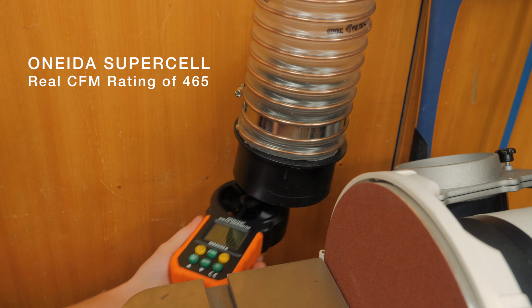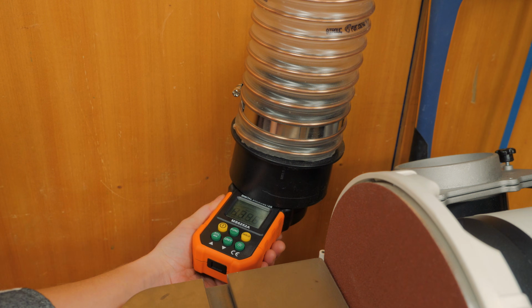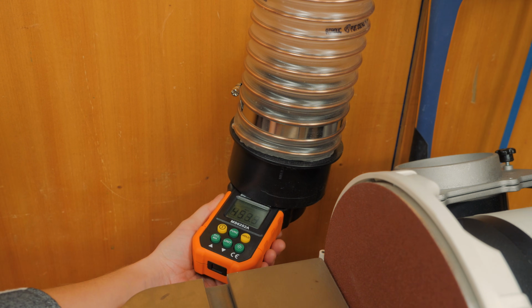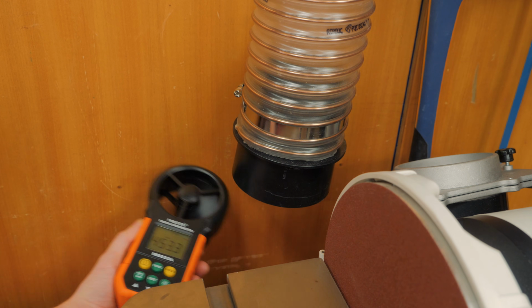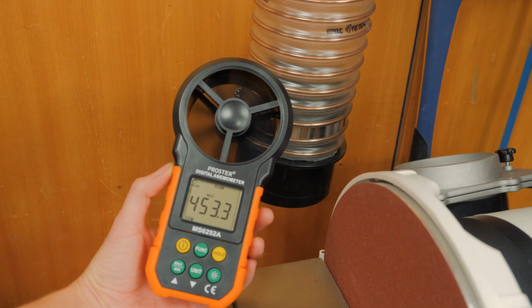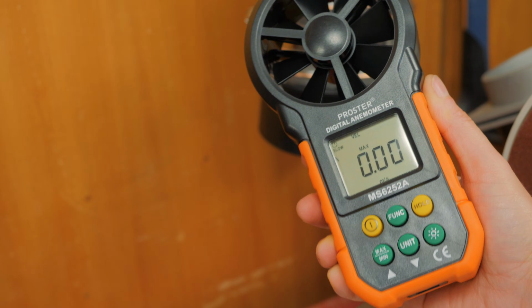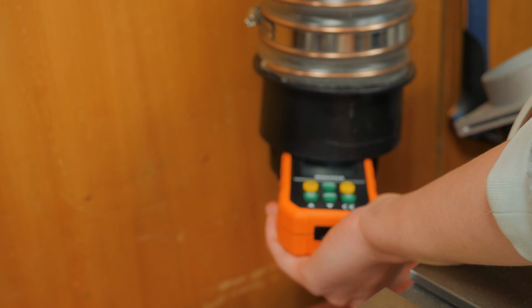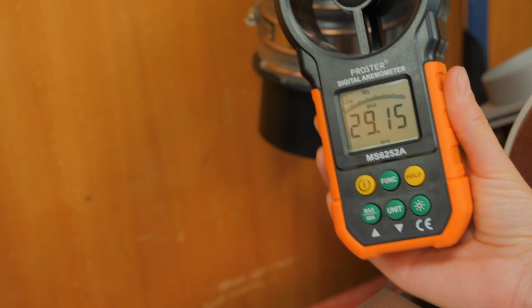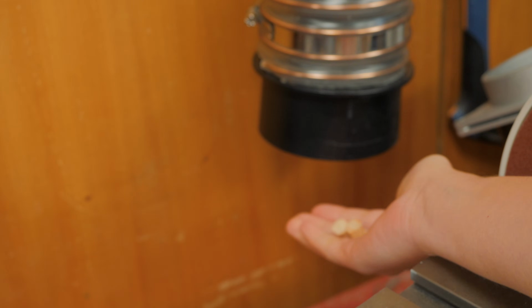Let's check the center port. This is where the airflow is better because it's mostly metal pipe with a very small section of hose. I'm getting 453 CFM here, which is very good considering I have several 90-degree turns in the ducting. And here we can see the air is traveling at almost 30 meters per second. So cool.